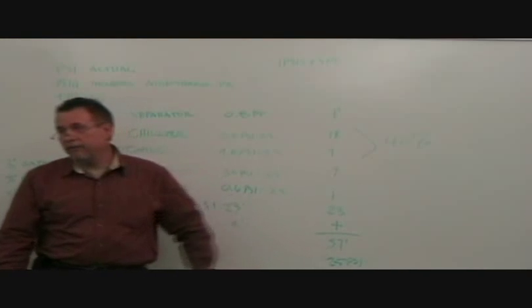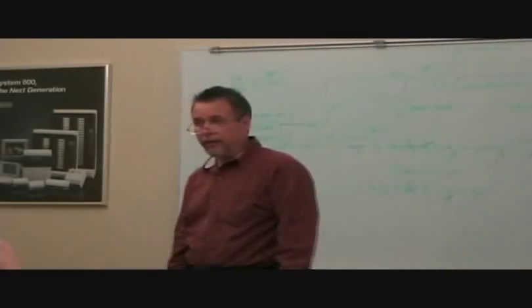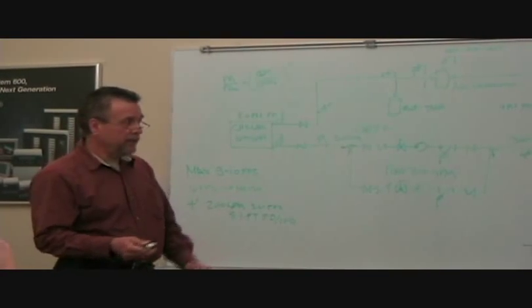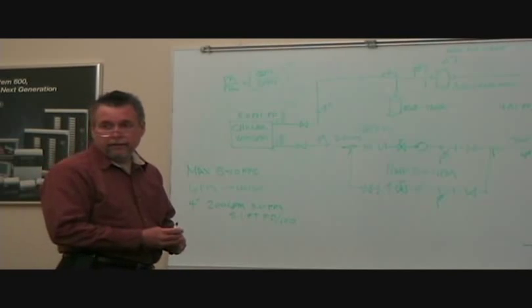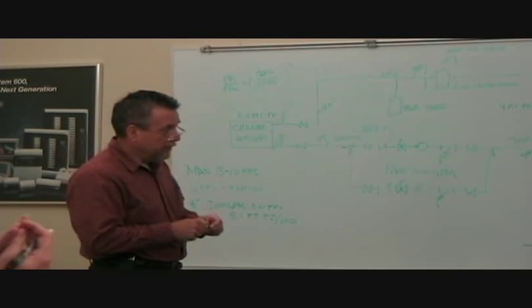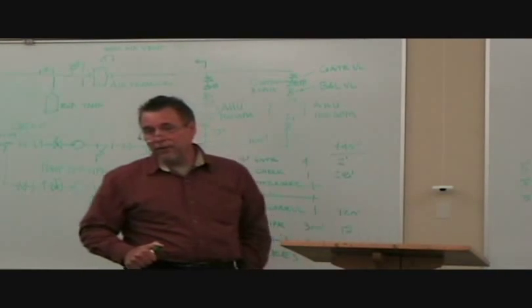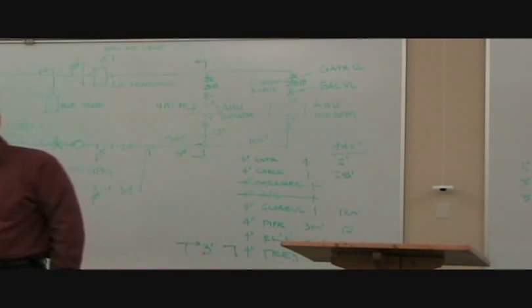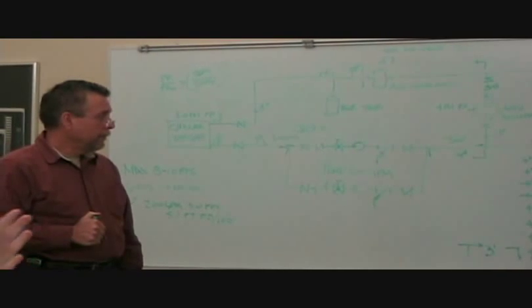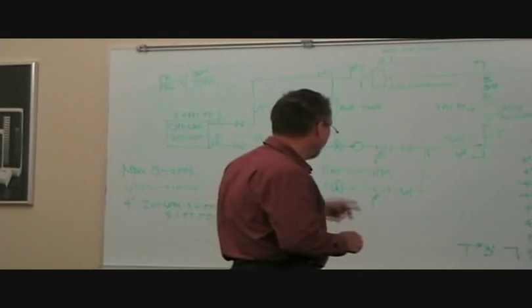What I would do, now as a designer, I'm just going to put a safety factor on that. And if I don't have a good set of drawings, the safety factor is higher. If I get a good set of drawings, then the safety factor is lower. And like I said the other day, there are some people that take things out to 2, 3 digits past the decimal. That's kind of ridiculous. But now I got a pump. I got to select these pumps.